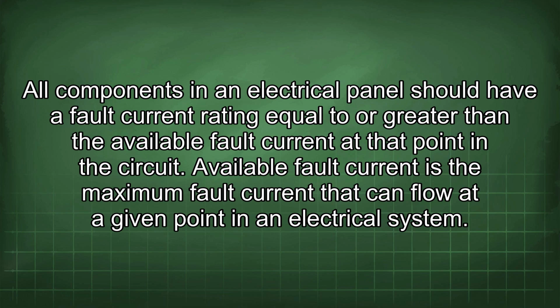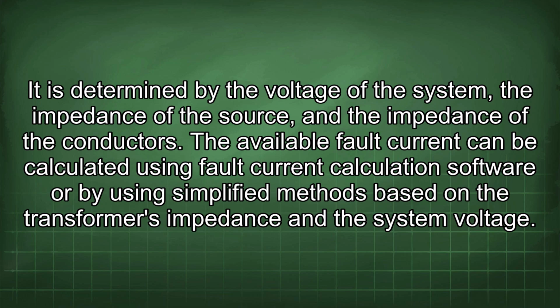Available fault current is the maximum fault current that can flow at a given point in an electrical system. It is determined by the voltage of the system, the impedance of the source, and the impedance of the conductors. The available fault current can be calculated using fault current calculation software or by using simplified methods based on the transformer's impedance and the system voltage.